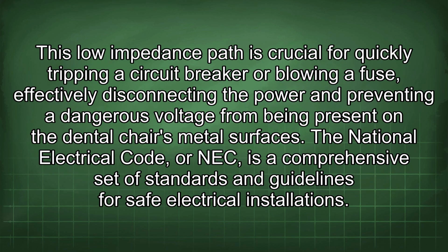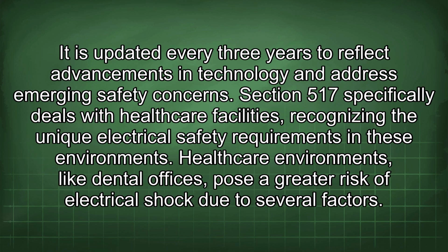This low-impedance path is crucial for quickly tripping a circuit breaker or blowing a fuse, effectively disconnecting the power and preventing a dangerous voltage from being present on the dental chair's metal surfaces. The National Electrical Code, or NEC, is a comprehensive set of standards and guidelines for safe electrical installations. It is updated every 3 years to reflect advancements in technology and address emerging safety concerns. Section 517 specifically deals with healthcare facilities, recognizing the unique electrical safety requirements in these environments.